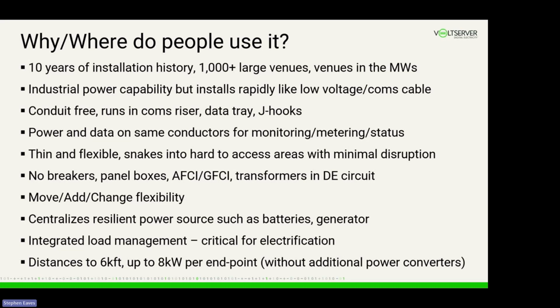People use it because it goes in very easily using low voltage, or what we would call limited energy installation techniques. So it has the power capability of conventional AC power, but it installs like Ethernet cable. It's conduit free, and it's qualified to run in risers, so that riser closets in buildings can carry digital electricity, or in data tray J-hooks. It's basically an IT installation.